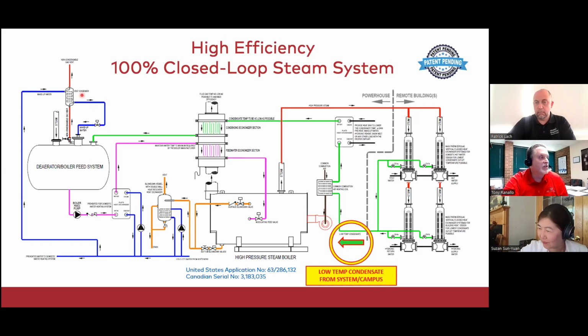Now, there are other things that we encourage. Nothing new here. Put a vent condenser on your deaerator. But because we're bringing back all this condensate, we've eliminated the flash losses, and we are really reducing the amount of makeup on the system. You can consider not having to have a deaerator at this point. You can go possibly with a boiler feed if all of your systems out in the buildings are vertical flooded heat exchangers, because we have no air infiltration. So something to consider there.